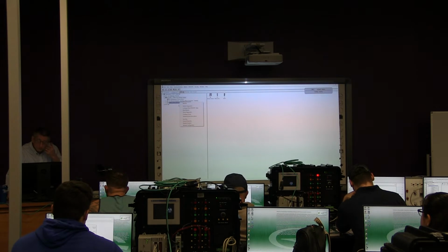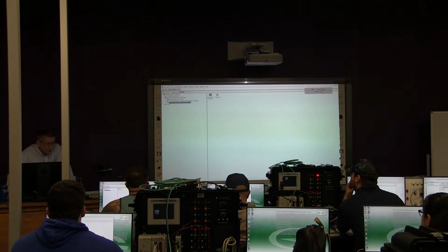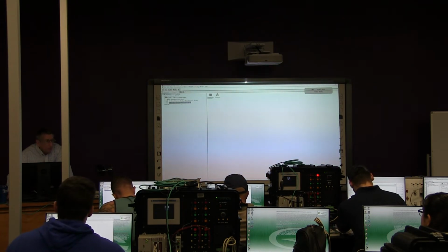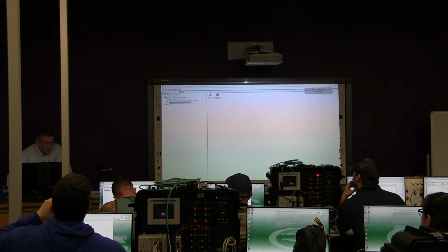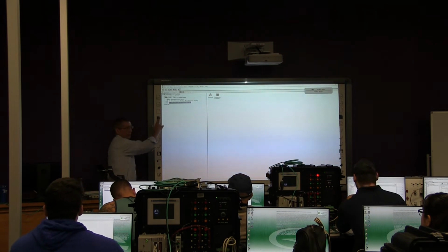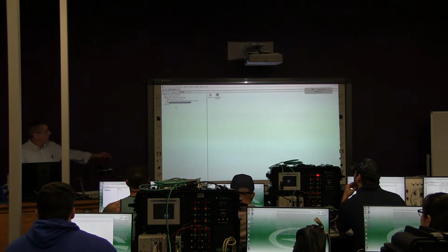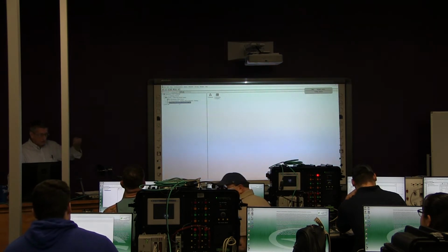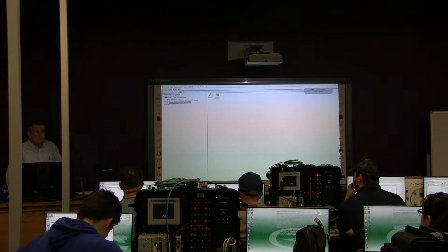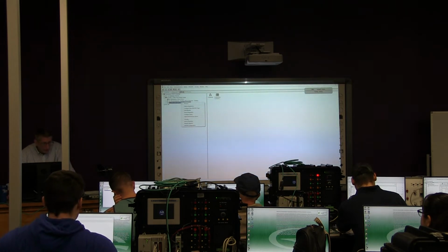You're on RSLinx, right? Module configuration. Does everybody understand that is the PLC? These PLCs are 1769 L24 ER QBFC1B. I see a lot of people fumbling around in this stuff, and all you gotta do is locate the PLC. It's pretty simple, not rocket science, so don't be fumbling around and wasting time. Just go right to the PLC. You basically plug in your USB, click on it, right click, and go to module configuration.